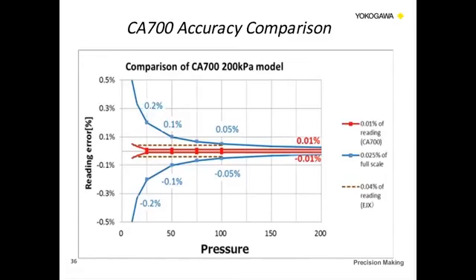So what you see here is that at the full range of the span, which is 200 kPa, the accuracy difference between the CA700 and some of the other competitive devices is not that big. You can see the lines are very close, but since ours is a percentage of reading, our line is going to be fairly linear across the span. Whereas with the blue line, as you get down to the lower pressure ranges, you have to add in the full error of the percentage of the span into the equation. So what that means is when you're measuring in the lower pressure ranges, you could potentially be off 20, 30, 40% in terms of what you're measuring. This is where we talked about the ability to replace multiple modules in many applications. To accurately measure and calibrate something in this range, you may need 2 or 3 different pressure modules, whereas with the CA700, that can be accomplished with one module across the entire span.